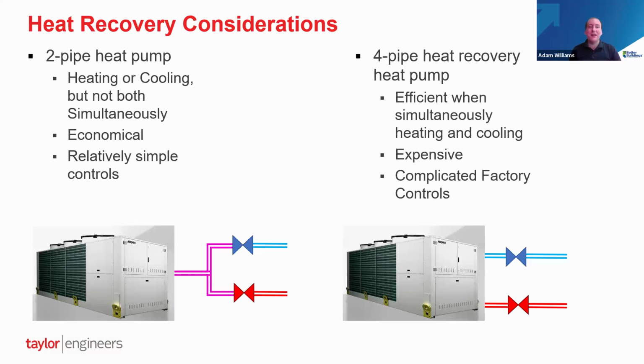The other option is a 4-pipe heat recovery heat pump, or heat recovery chiller, sometimes called. These allow you to do simultaneous heating and cooling, and they can have the evaporator be the chilled water side and the condenser be the hot water side. So you can recover heat from your chilled water to your hot water loop, which is more efficient when you have to do simultaneous heating and cooling. The problem with these is they're more expensive and they have more complicated factory controls, because the factory controls generally decide whether you're running in heat recovery mode, whether you're rejecting to the outdoors, and the staging for heating and cooling. So it can get more complicated.